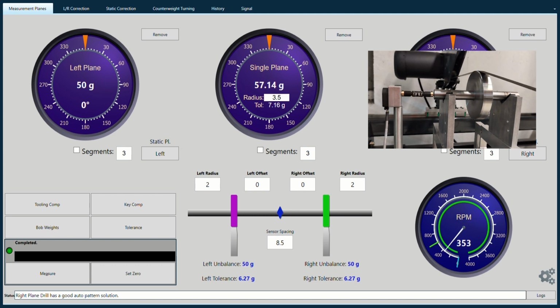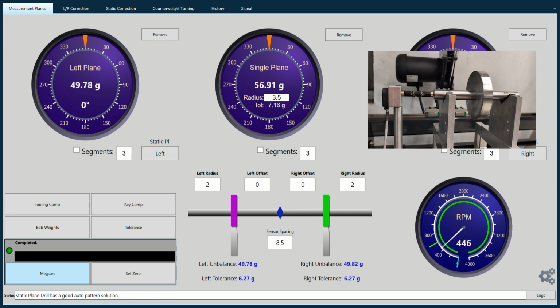Spin the part up to your calibration speed again and take another reading. The numbers on the left and right plane should now be within approximately 0.3 grams of what is indicated on your arbor. If the numbers are not within this range, press Calibrate again and take another reading. Repeat this process until you are satisfied with the reading, taking multiple spins to verify that it's maintaining. The angle should read 360 or 0 after calibration.